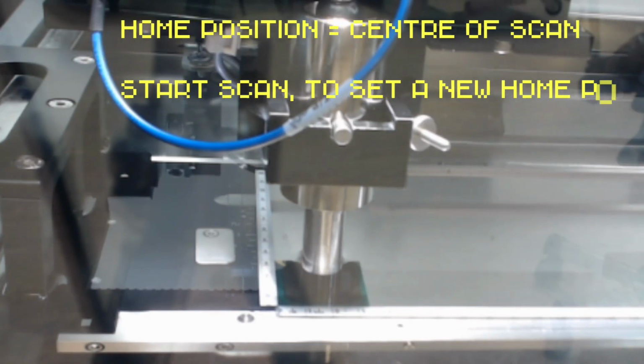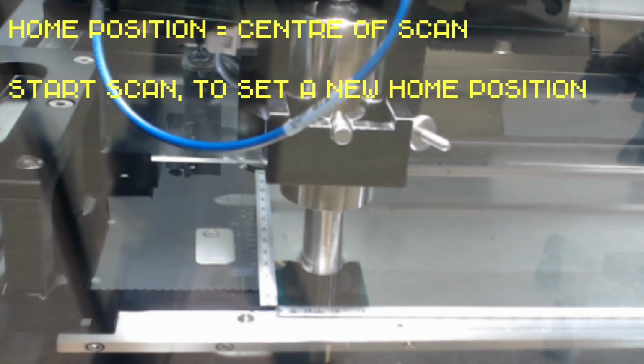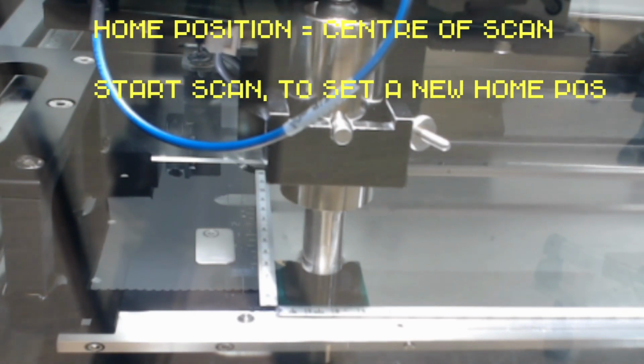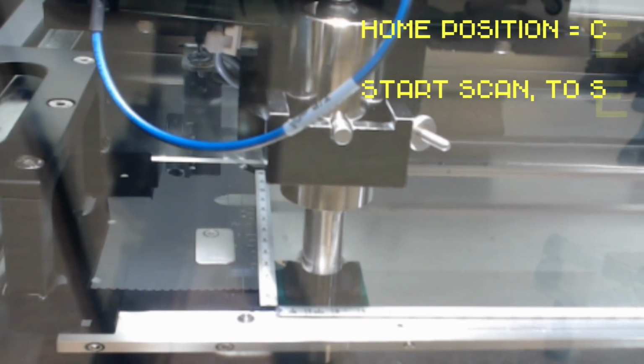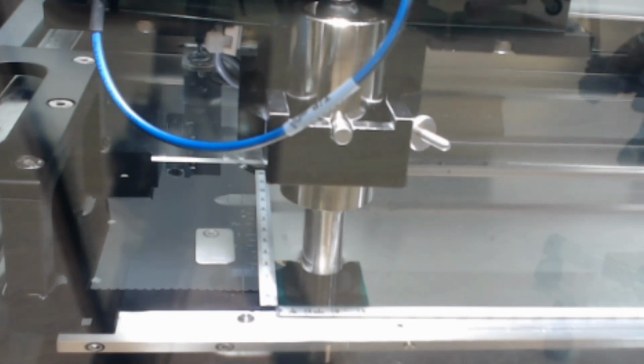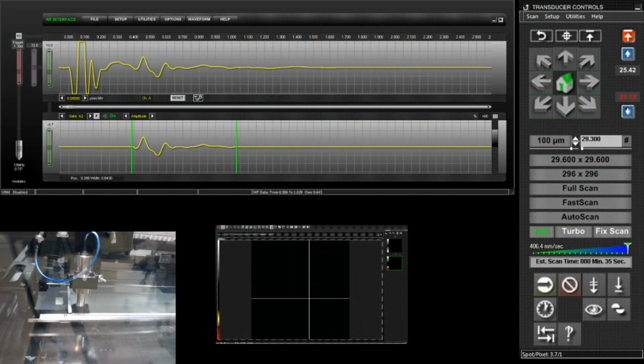So now we have the transducer perfectly in the center of the sample, and this is what we call the home position. So every time you stop a scan, it will return to the home position, center of the sample. So if we just return to the software screen, okay, there are 5 steps that we need to run through before performing our initial scan, and we'll run through those now. The first 3 steps will be your focus, your gate position, and gain adjustment. Focus, gate, gain.